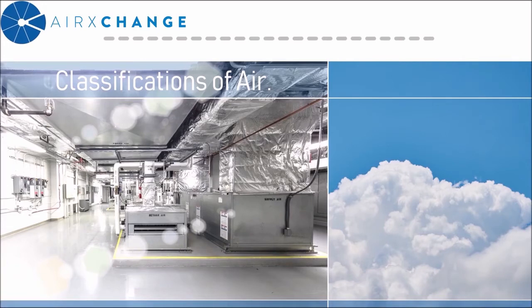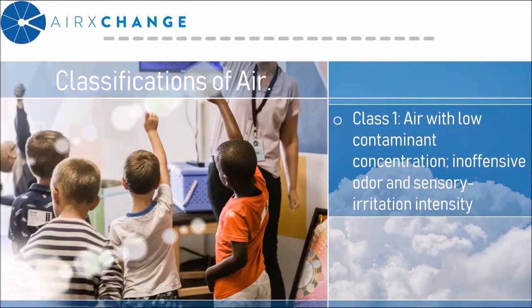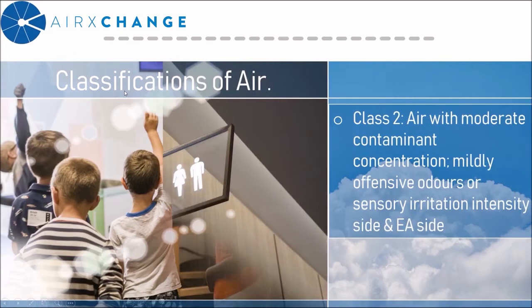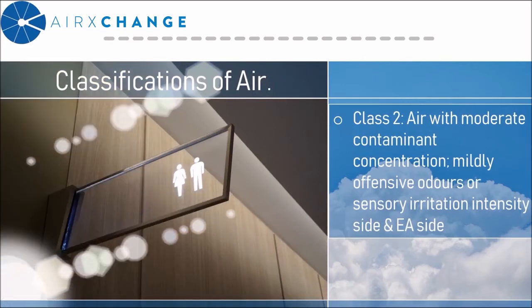Let's take a closer look at the ASHRAE ventilation standard. Within the standard there is a section for air classification and recirculation, which aggregates different space types and their relative level of contaminants and provides a method to determine the appropriate amount of leakage. The air is divided into four different classes: Class 1 through 4. Class 1 is air with low contaminant concentration and inoffensive odors — examples include classrooms, office spaces, assembly rooms, churches, and corridors. Class 2 is air with moderate contaminant concentration or mildly offensive odors — examples include restrooms, swimming pools, dining rooms, and locker rooms.